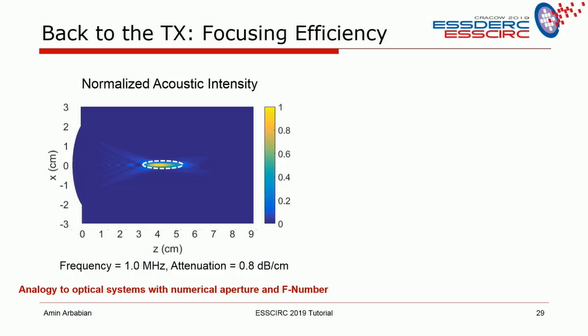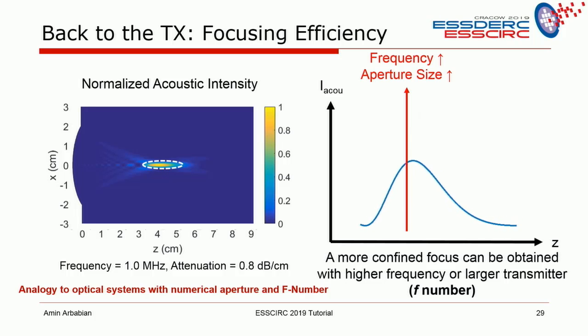So you have a depth of field, the length of the focus, and a lateral focusing capability—usually the lateral focus is better than the depth of field. So you end up with this grain-of-rice picture. The dimensions of this grain of rice are controlled by two fundamental parameters: aperture and wavelength. As you go down in wavelength or up in aperture, the focusing gets better. So if you compare an F3 transducer with an F1 transducer—where you're coming closer and the transducer is bigger—it has much better focusing. That's the effect we're showing here.